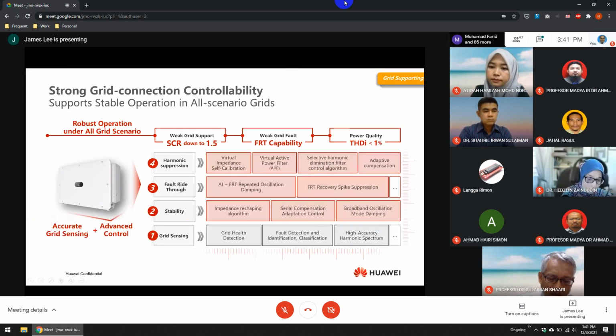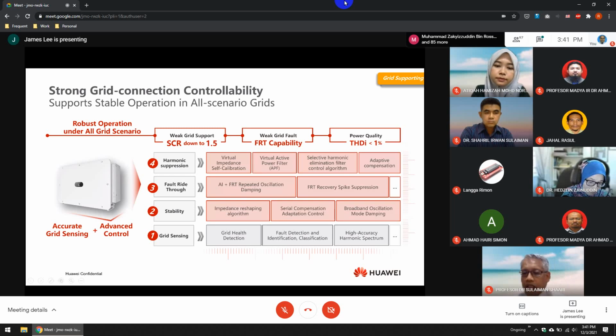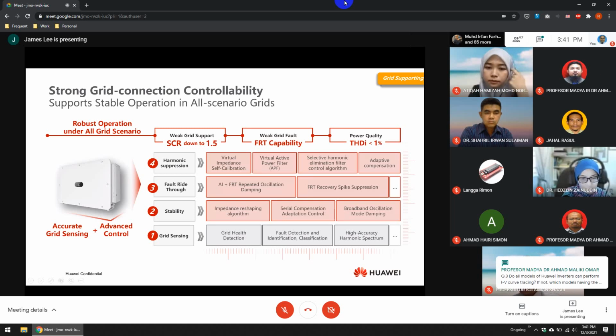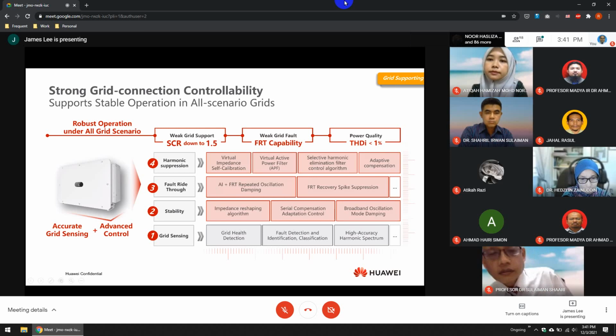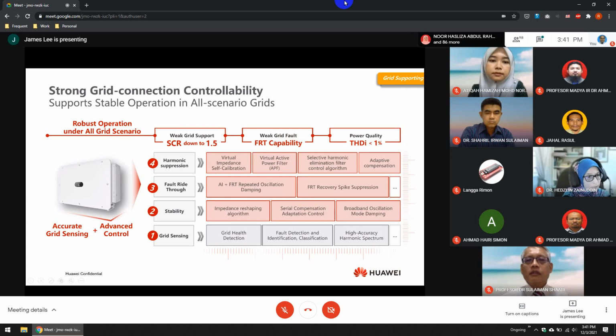This is grid supporting, my last topic of discussion. As there's more penetration of PV systems or renewable energy systems, short circuit ratio will become a key factor, and some weak grid support down to even 1.5 SCR. Because of that, the fault ride-through capability has to be increased and improved, and your power quality also has to be a lot more stringent.